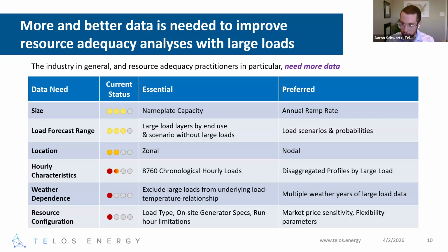There's a range of data needed, from the most basic, like how big are the large loads we're considering, to incorporating uncertainty through a load forecast range. Most critical are these hourly characteristics for functionally allowing us to model flexibility in resource adequacy assessments and capacity expansion modeling. We really want 8760 chronological hourly loads, ideally disaggregated by individual load types.